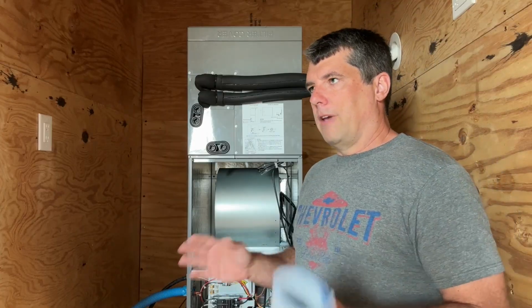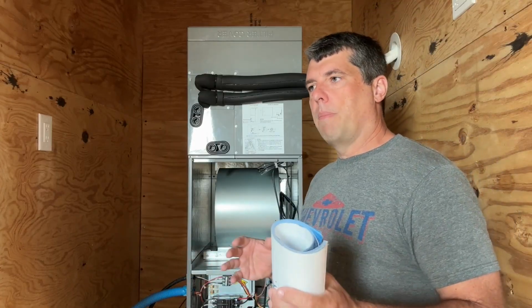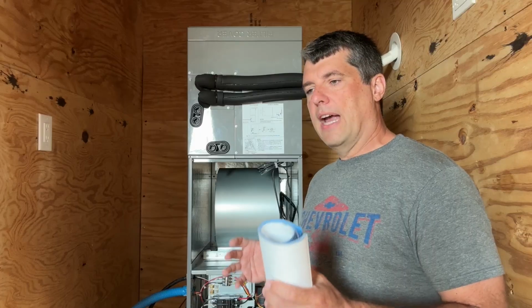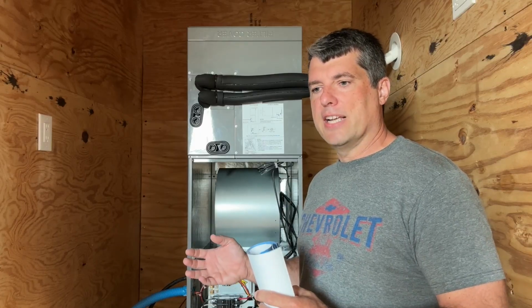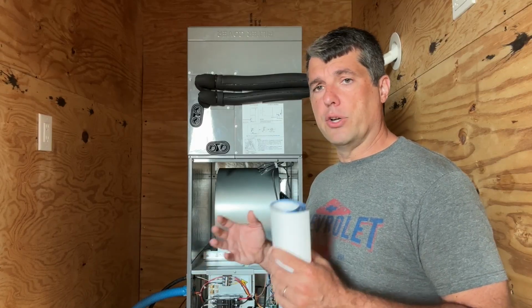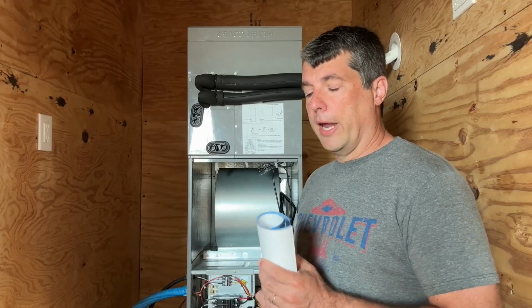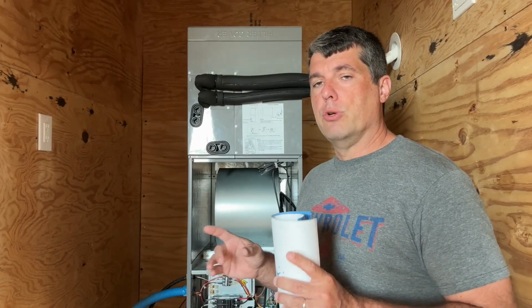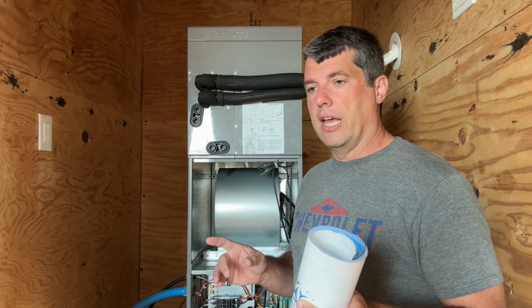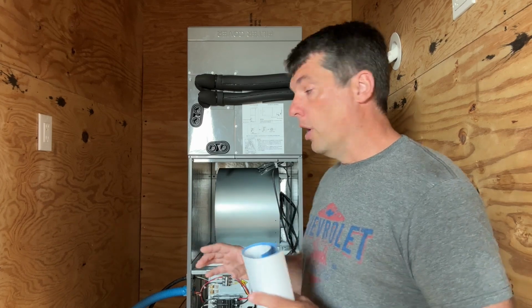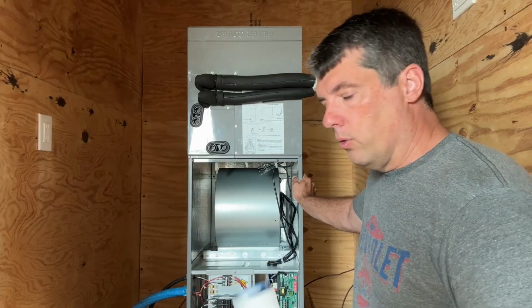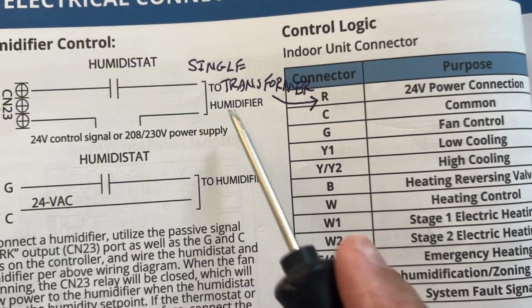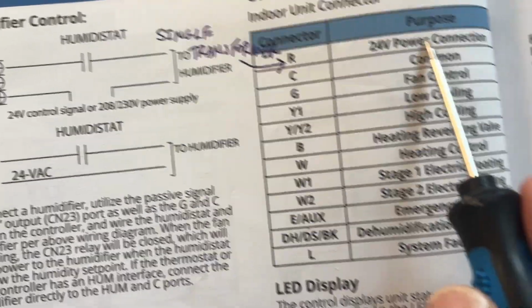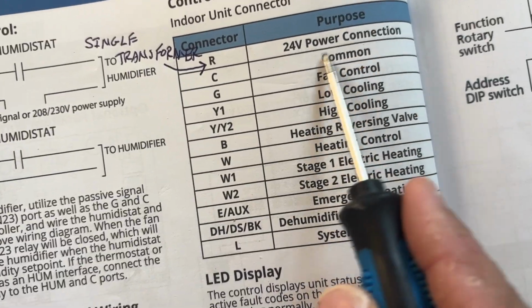In gas forced air systems, typically it's going to be a dual fuel system, in that you're burning gas to create the heat, and you're using a heat pump for the cooling. In that scenario, you're going to have two transformers, a heating transformer and a cooling transformer. In this scenario, you have one transformer because two's not needed. You have the switching valve, or the reversing valve, to do the switching for you.